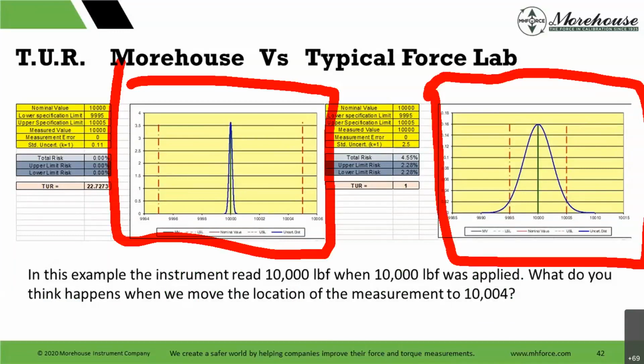They may be better than this. I'm just using a number like 0.4, and it depends on what you put in as tolerance. But look, each one is reading 10,000 pounds. A little bit of this graph is hanging over here. Nothing's really hanging over here when you're doing it with dead weights. Why? Because the largest uncertainty contributor in this example is the reference standard used for calibration.